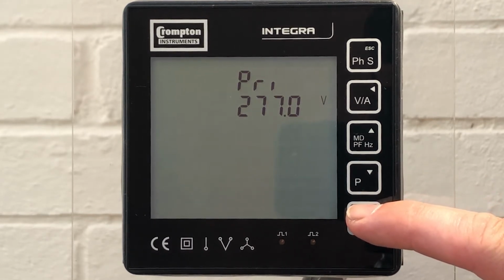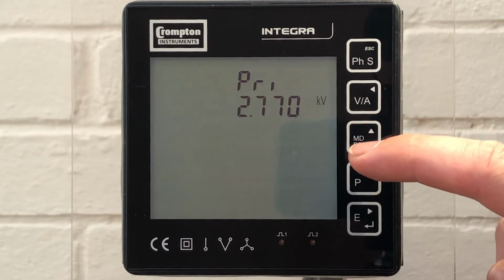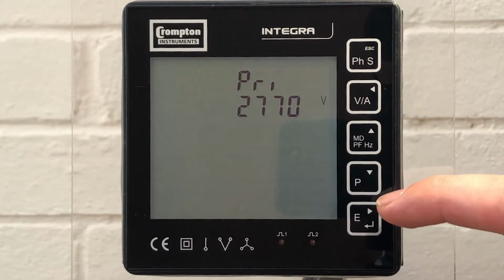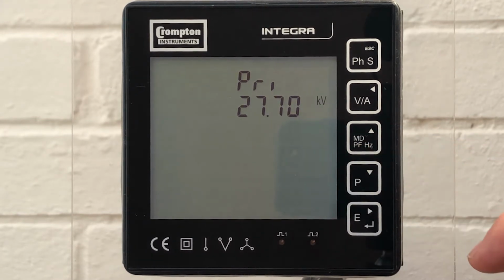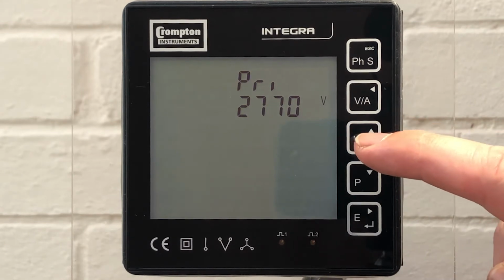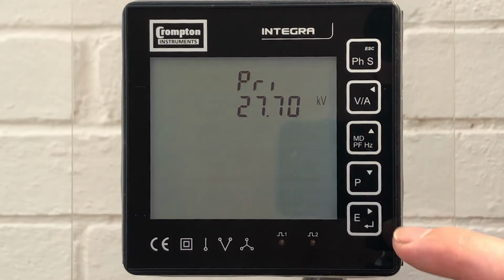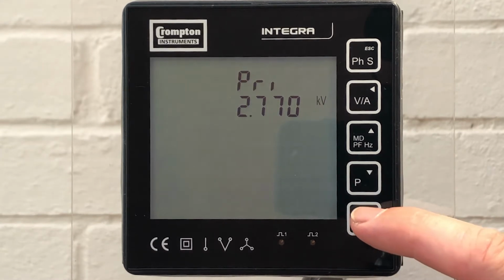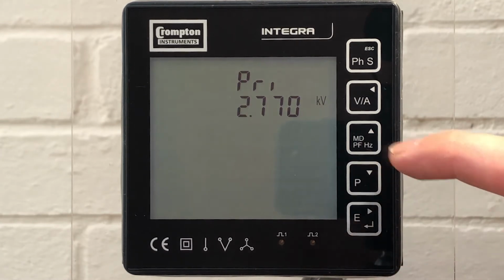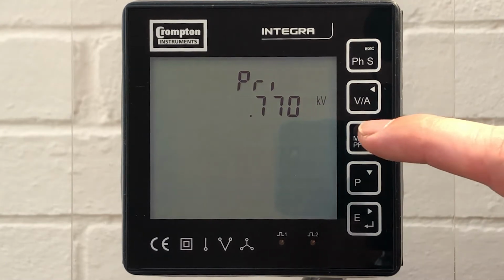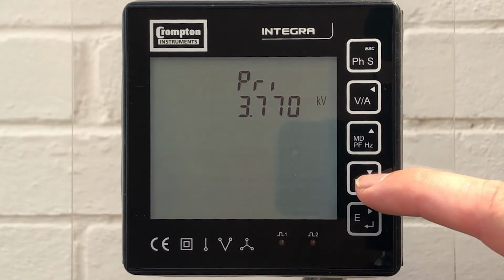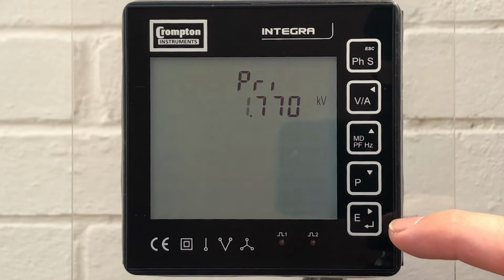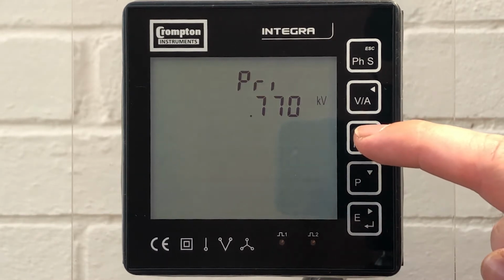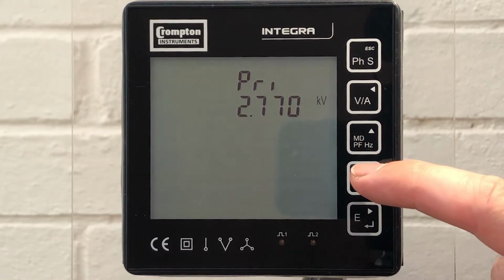If you're not using a voltage transformer, simply leave this voltage as 277. If you are using a voltage transformer, this is where you can enter the primary voltage of that transformer. We're going to set our primary transformer in kilovolts.